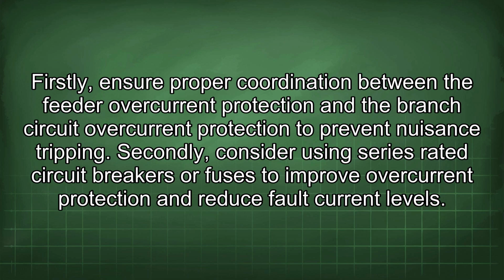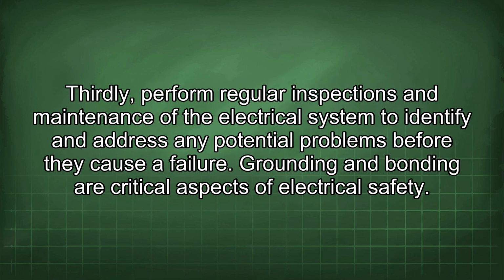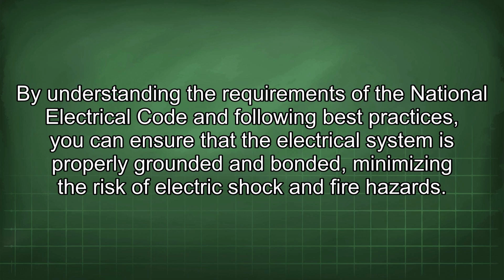Secondly, consider using series-rated circuit breakers or fuses to improve overcurrent protection and reduce fault current levels. Thirdly, perform regular inspections and maintenance of the electrical system to identify and address any potential problems before they cause a failure. Grounding and bonding are critical aspects of electrical safety. By understanding the requirements of the National Electrical Code and following best practices, you can ensure that the electrical system is properly grounded and bonded, minimizing the risk of electric shock and fire hazards.